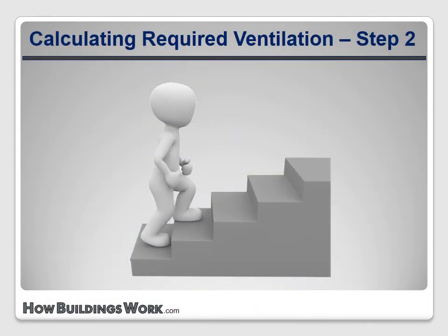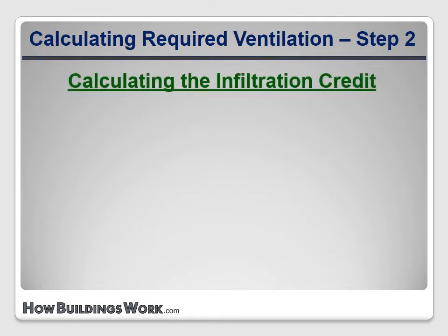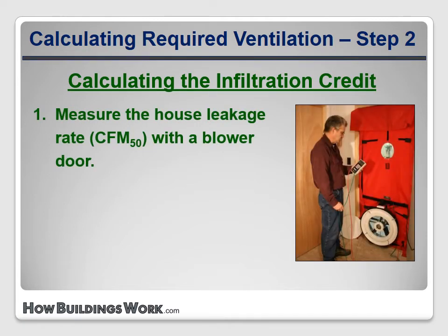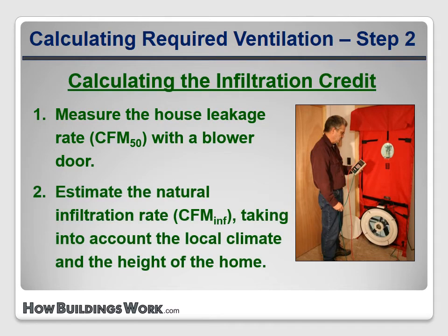Remember, that number we calculated is the total desired ventilation rate, but some of that is satisfied by natural air leakage. So the next step is that we get to apply an infiltration credit. We know what the blower door reading is — 850 CFM — but that's the leakage rate at the 50 pascal test pressure. We need to use that blower door reading to estimate the leakage under normal, natural conditions, using the local climate and the height of the house.